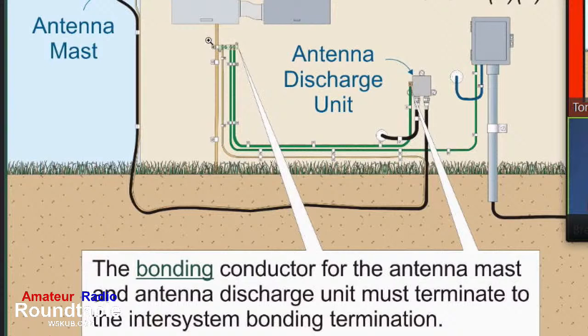And you should have a wide ground field to make sure you get some decent connectivity to the earth. But then they also need to be bonded back to this intersystem bonding termination. When you do that, you have to use at least 6-gauge wire, which is pretty thick. I actually go one thicker, and I would normally use number 4, or even bigger than that. The lower the gauge number, of course, the thicker the wire.